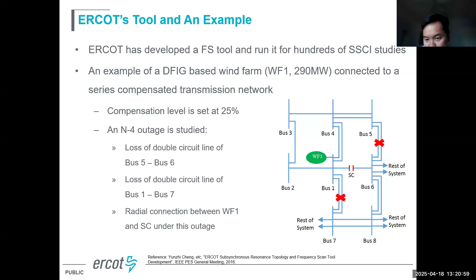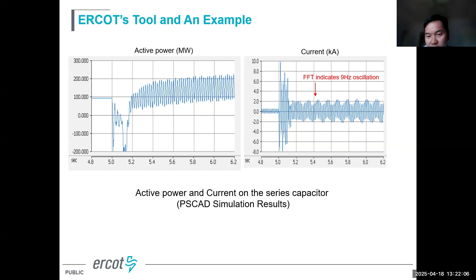What we found is that the reactance crosses from negative to positive at 8 to 9 Hertz. And at the crossover frequency, the resistance, the blue one, is negative, which indicates risk of SSCI. Then we performed a PSCAD study for the same contingencies, and we do observe the SSO phenomena. We also ran FFT studies using the current, and the FFT indicates the oscillation is at 9 Hz, which matches the frequency scan. So for SSCI, the frequency scan looks like a pretty good screening tool. So far, everything is good.